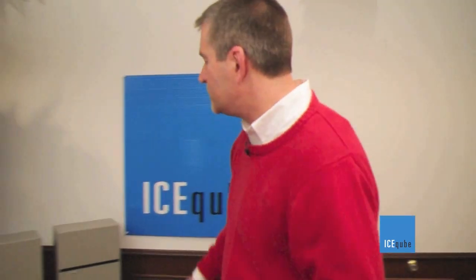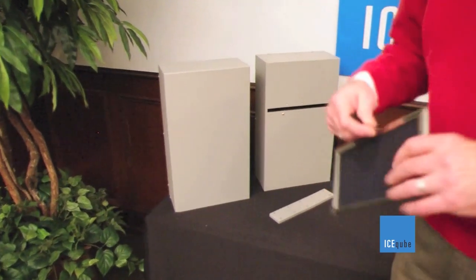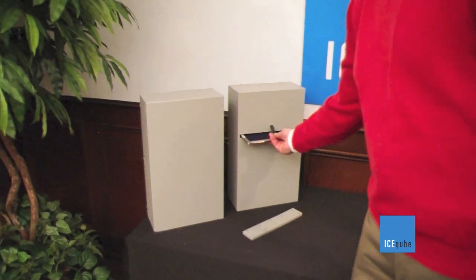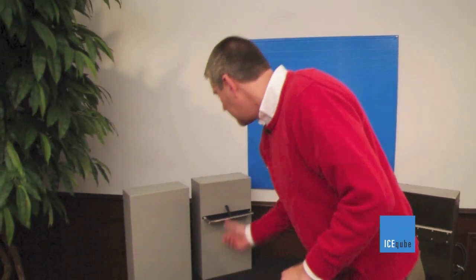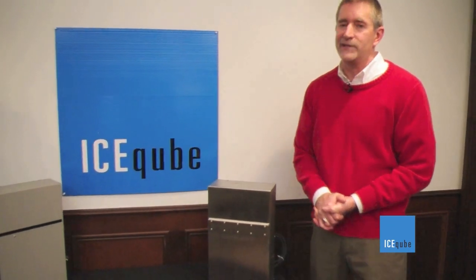The typical package includes both an intake and an exhaust. The intake is supplied with a 10 micron polypropylene filter that is easily accessible for cleaning with a gasketed filter cover. The NEMA 4 application is a gray powder coat finish on top of 16 gauge carbon steel. The NEMA 4X application is available in both 304 or 316 stainless steel, and voltage options are 120 or 230 volts AC.